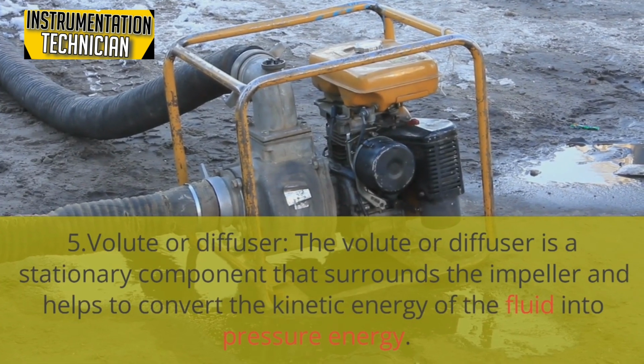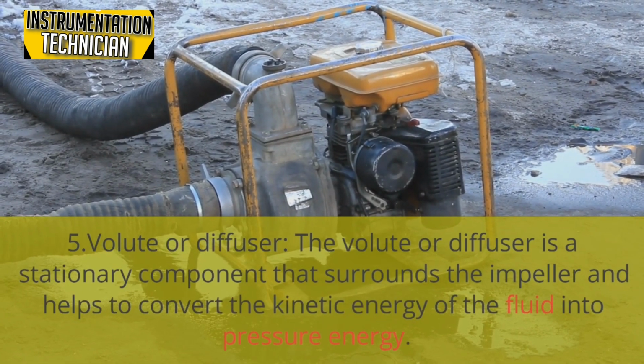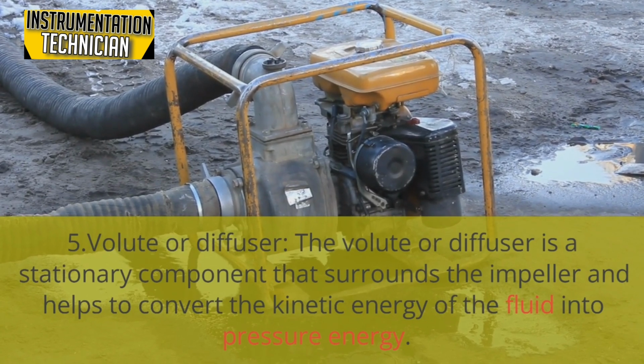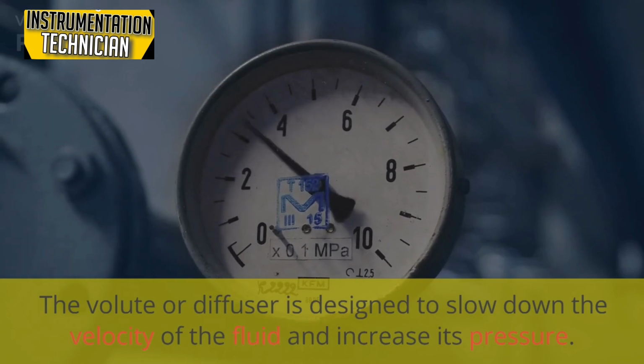5. Volute or diffuser. The volute or diffuser is a stationary component that surrounds the impeller and helps to convert the kinetic energy of the fluid into pressure energy. The volute or diffuser is designed to slow down the velocity of the fluid and increase its pressure.